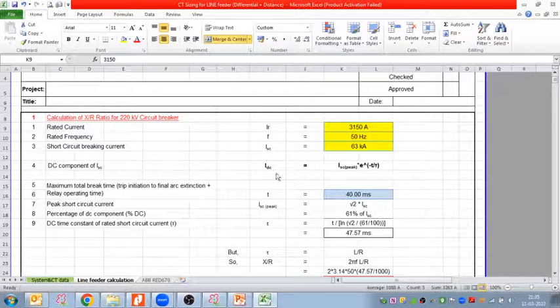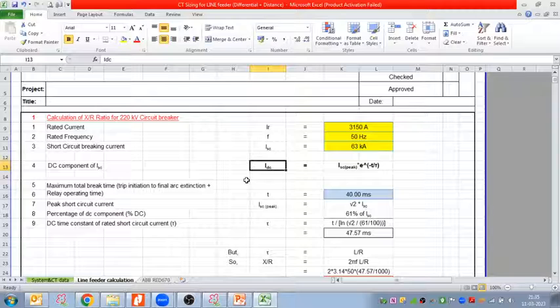Right, DC component. This is the formula to calculate the DC component in the short circuit current ISC. As I told you, when a fault happens, the fault current has both AC and DC components. So how much would the DC component be? You can calculate it with this formula: DC component equals ISC peak times e to the power minus t divided by tau.